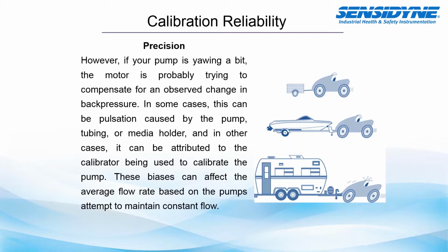So if you're taking multiple samples, you may average out to get an accurate measurement, which is what your desired flow rate is, but it might be going really high, really low. It could change the accuracy. And if you're making adjustments to the pump based on this, when you disconnect it from your calibrator, it might actually be flowing at a different rate than what you saw while it was connected to your calibrator.